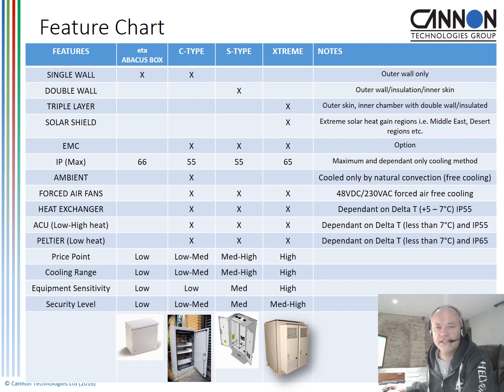SType range, this is a double walled cabinet, which has got an outer skin and then an inner insulated and an inner skin. It provides a high degree of protection of equipment which is sensitive to rapid changes in temperature, but also gives a high degree of protection with humidity, so helps maintain temperatures which fall below the dew point, so that condensation and water droplets aren't formed inside the cabinet. Typically it's an IP55 cabinet. We tend to cool either using forced air cooling, heat exchangers, air conditioning, or Peltier devices.